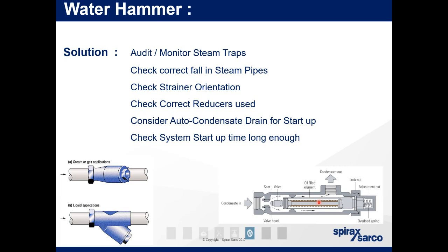If that's in a confined environment, say you have 7-bar condensate, now all that condensate suddenly turns to flash steam. It fills the area because of the volume. It could be potentially dangerous, life-threatening.